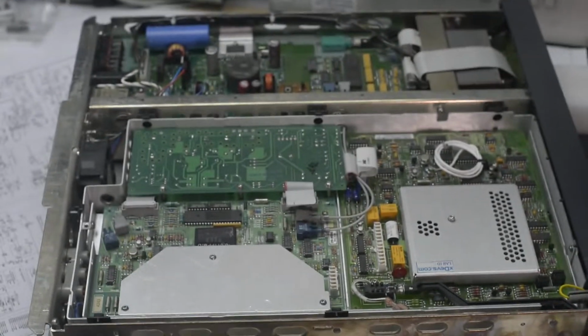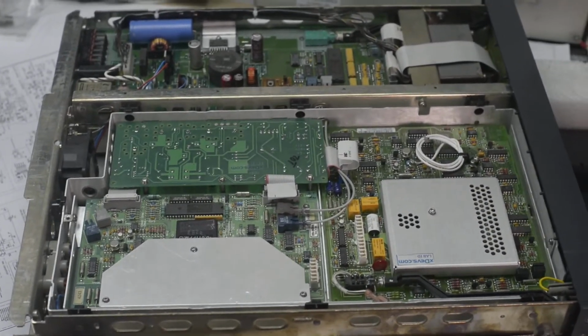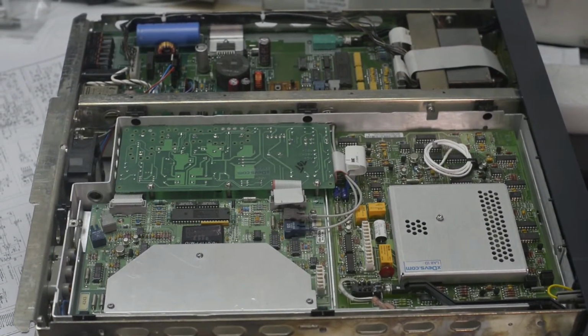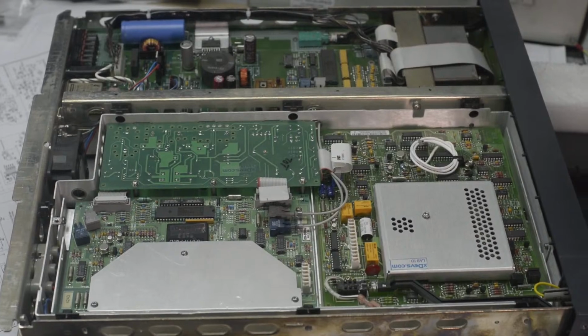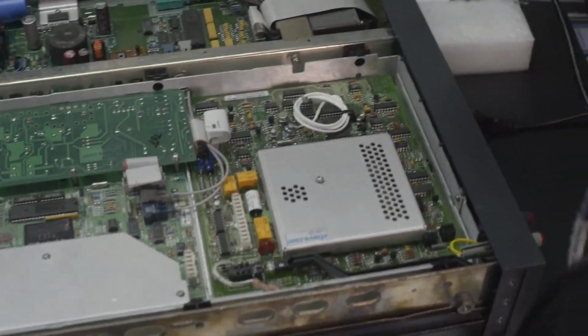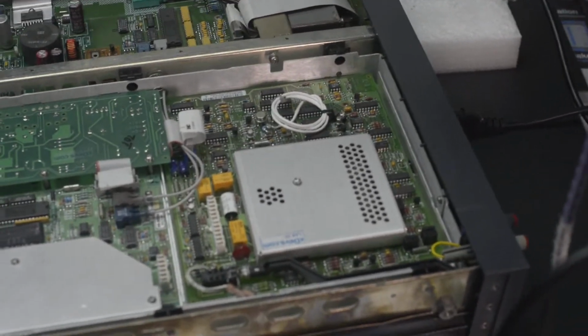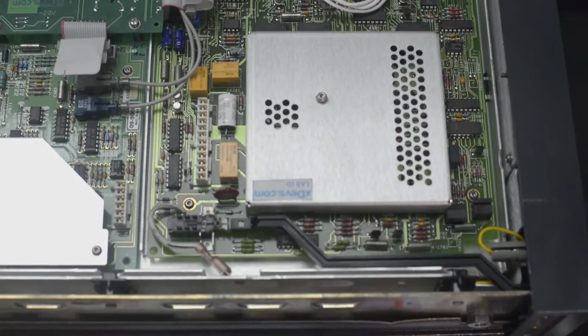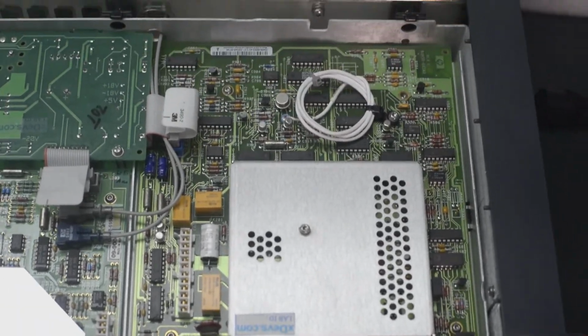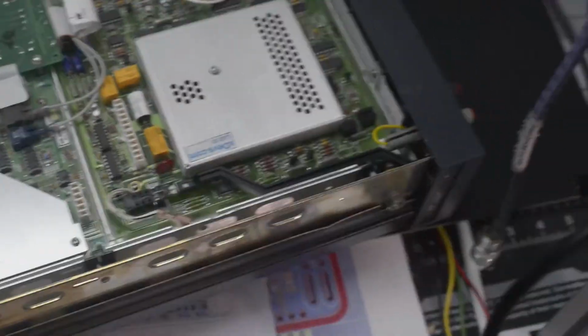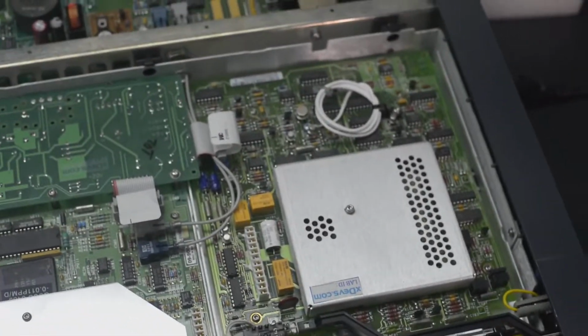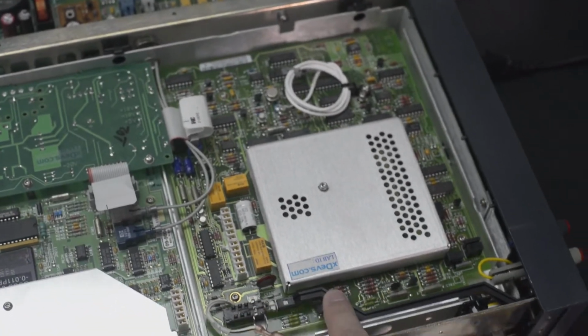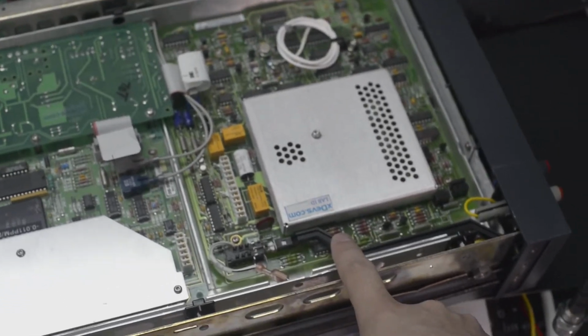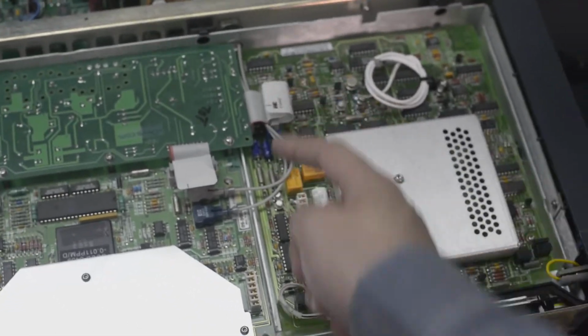So this is the insides of the box, and what we will do is replace the faulty A2 board, power it back up, and test what issues we have. The process is pretty straightforward. Unscrew some of the bolts, remove the guard rod, this guy, and this cable, and that's it.